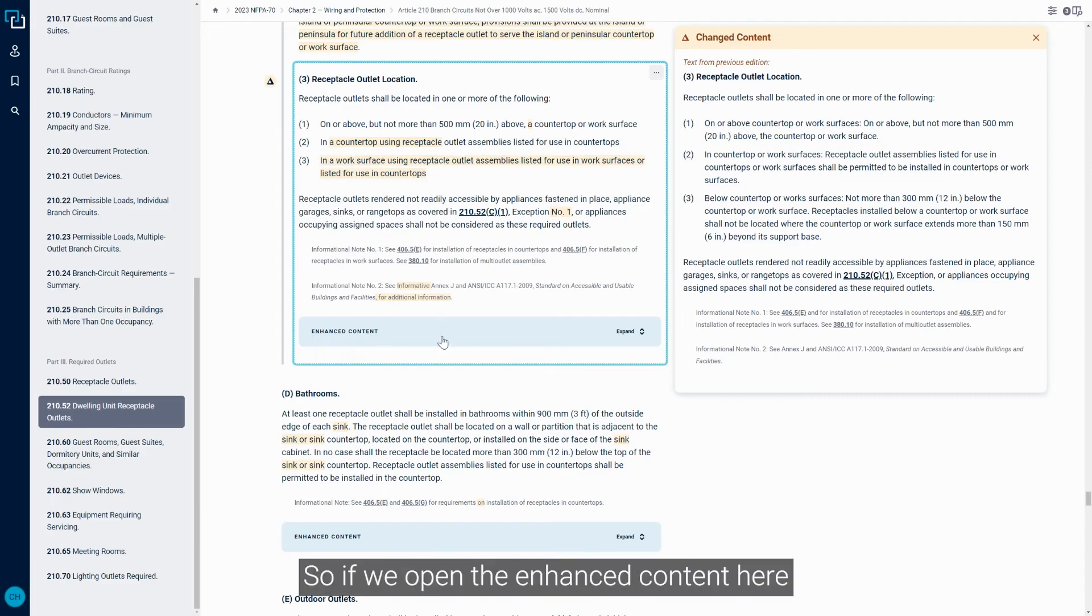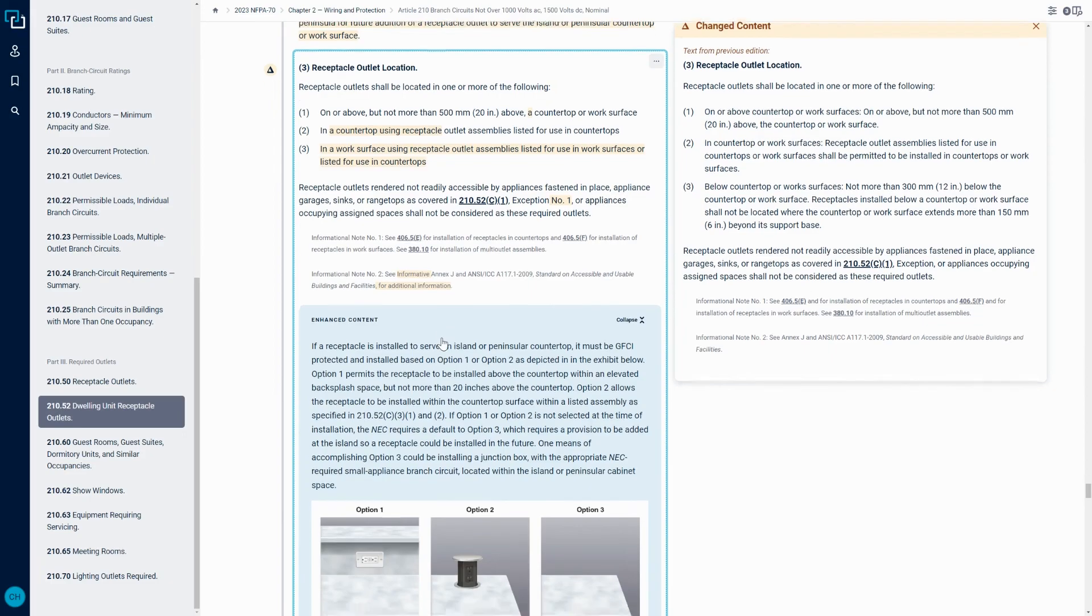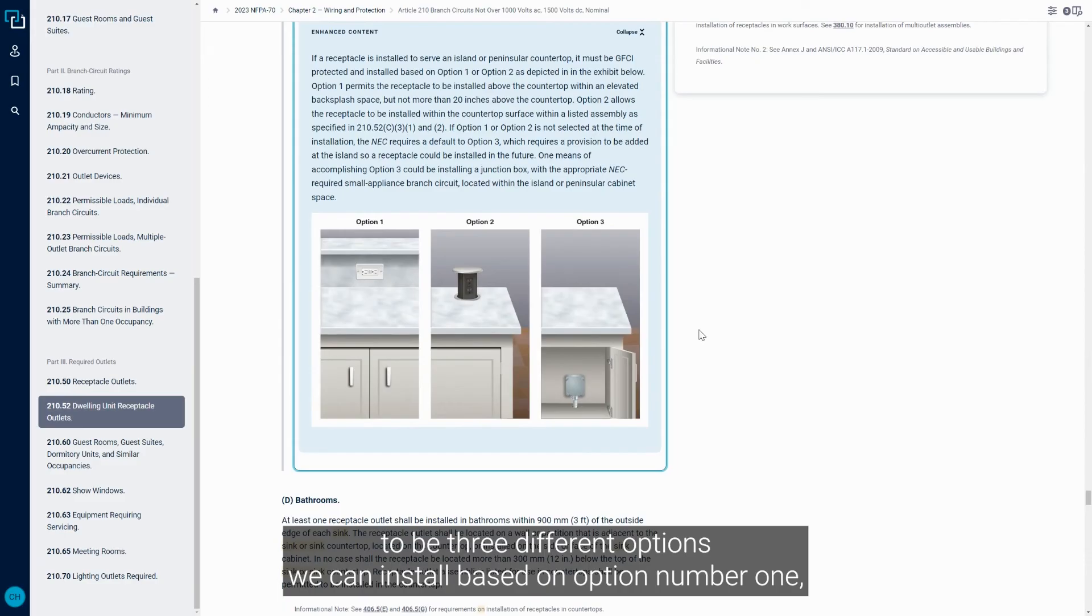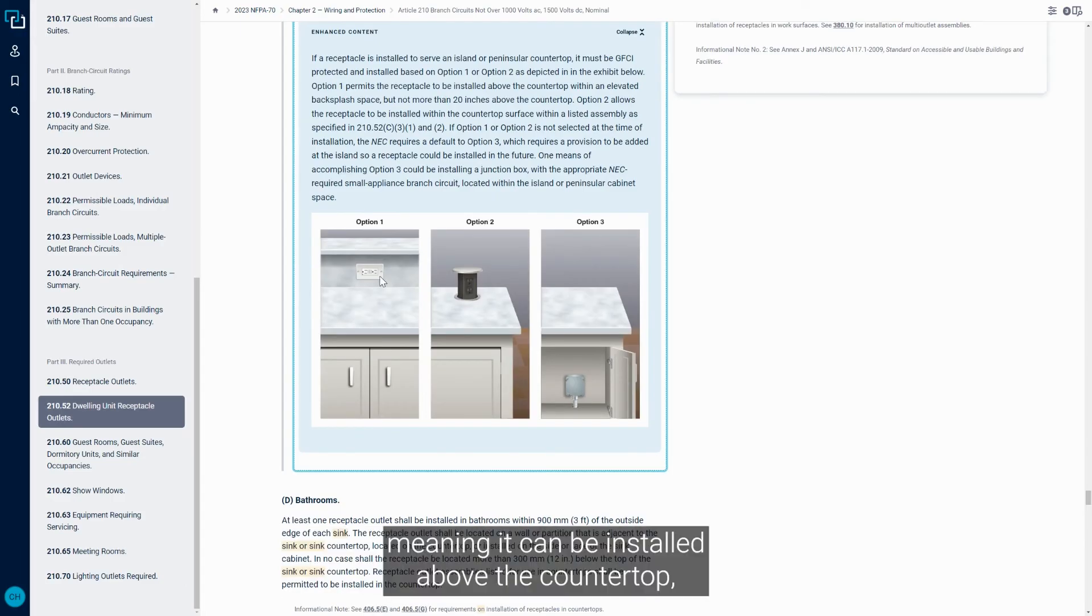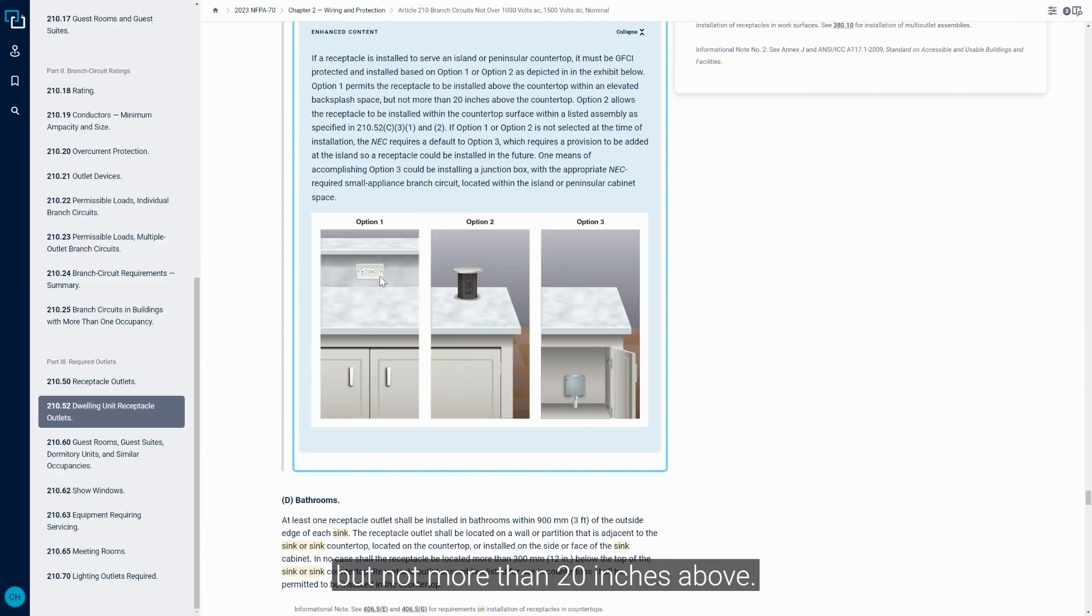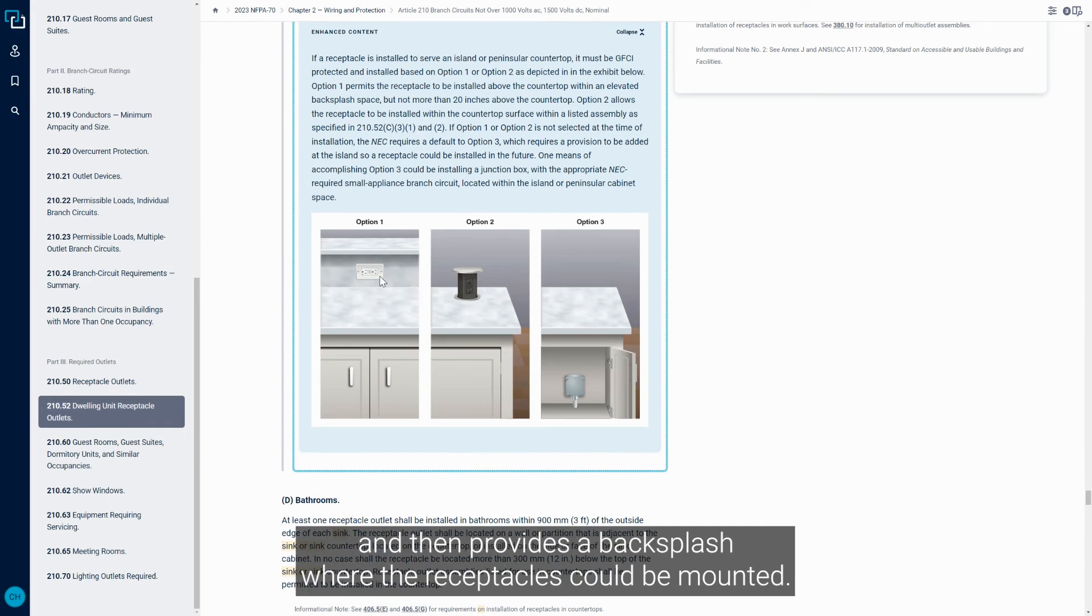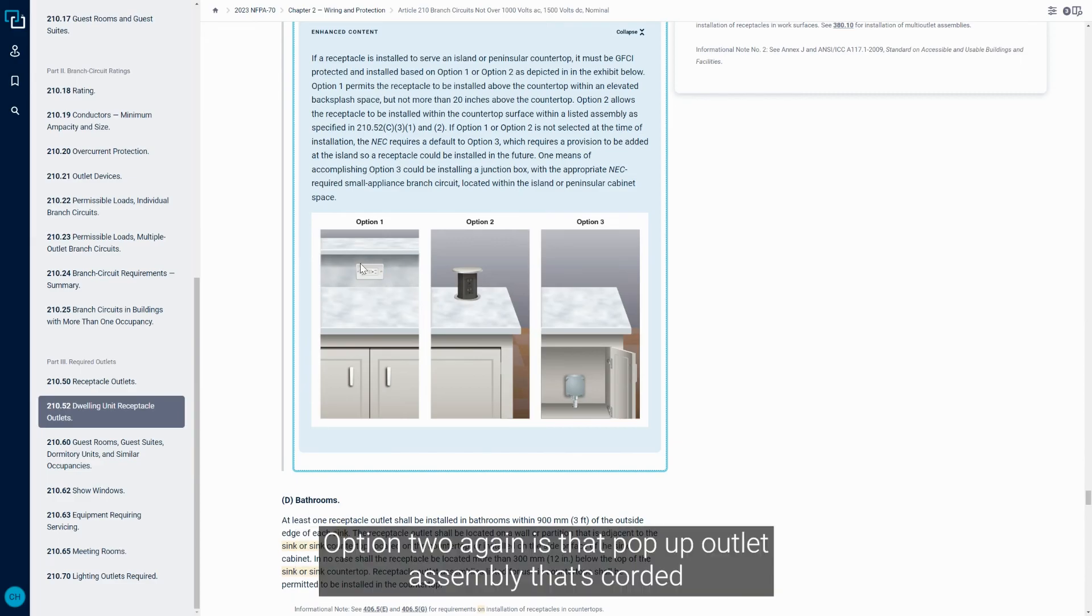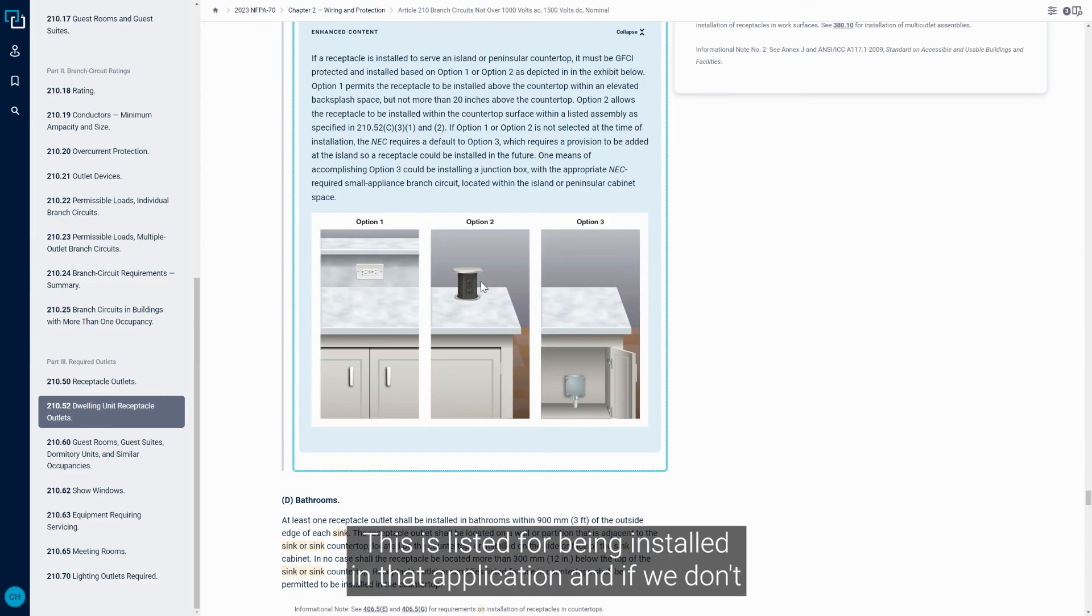So that's a big change. So if we open the enhanced content here in the 2023 NEC, it gives us essentially what turns out to be three different options. We can install based on option number one, meaning it can be installed above the countertop but not more than 20 inches above. So these applications are going to be island or peninsulas that typically have that second tier that steps up and then provides a backsplash where the Receptacles could be mounted. Option two again is that pop-up outlet assembly that's cored right into the countertop or work surface, but it must be an assembly that is listed for being installed in that application.